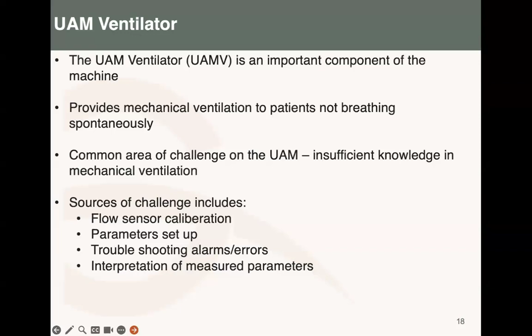We understand that the challenge of mechanical ventilation is a challenge to everyone, but in our training we always emphasize this, which is why when we pick a site we consider whether they may have that experience. I have some users I had to advise to start with volume control, because with volume control you just set your limit, set your tidal volume, set your rate, and you're okay. These are some of the challenges we've picked up, and if you've encountered similar issues, we can discuss more later and come up with a way forward.